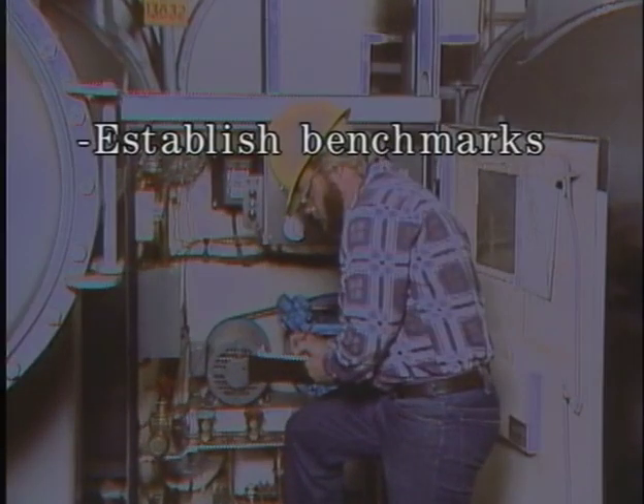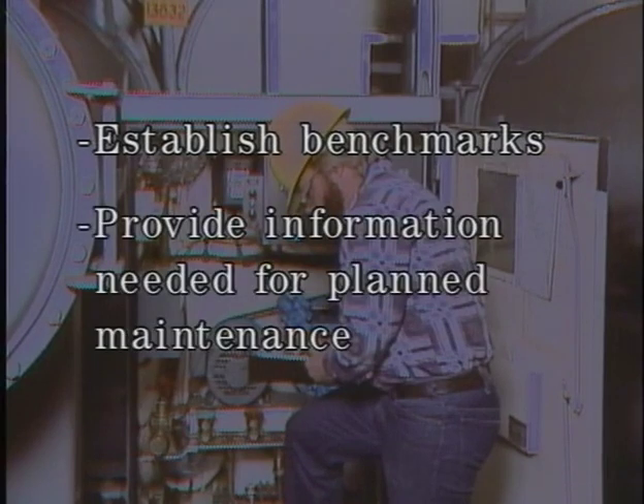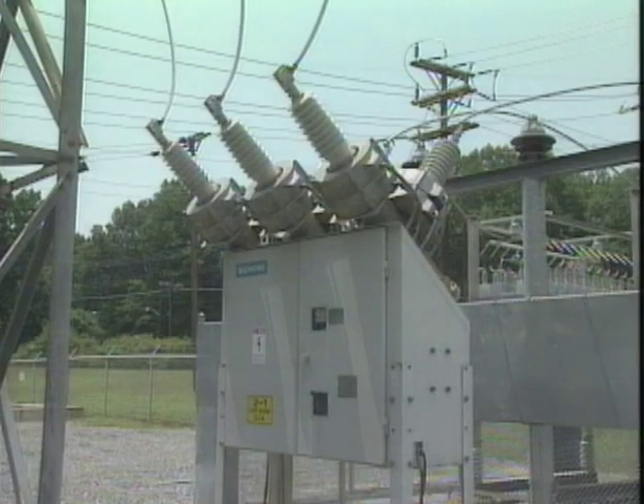Thorough documentation of the status of a new breaker before it's put in service establishes benchmarks for future inspections. All future inspections will be compared to the information documented at this time. In addition, the documentation from this inspection, as well as from future inspections, provides the type of information needed to develop and carry out an effective planned maintenance program. The documentation should include the status of each inspection item.